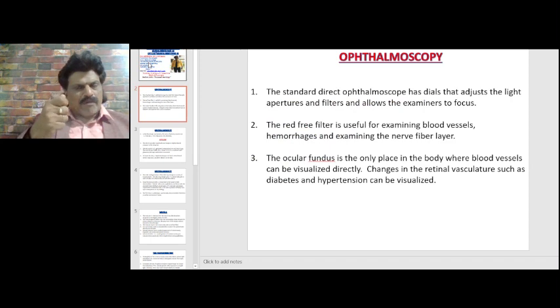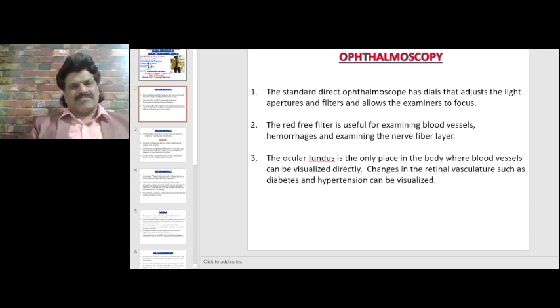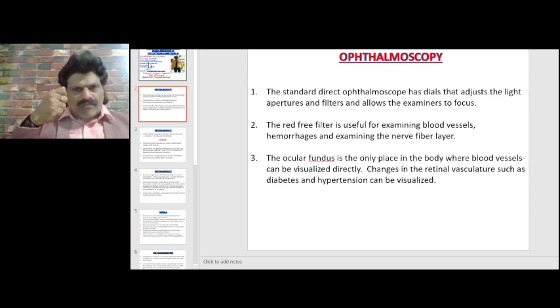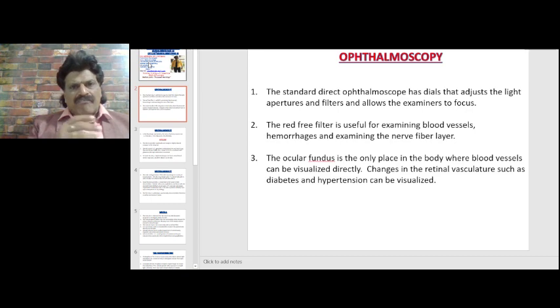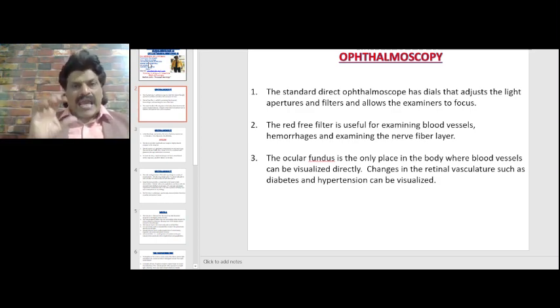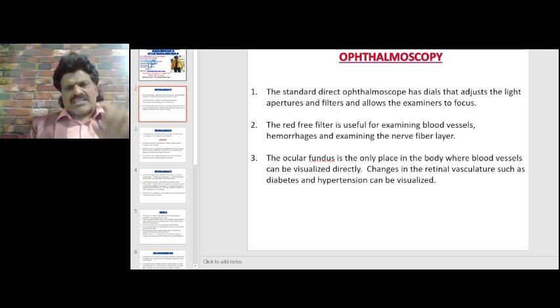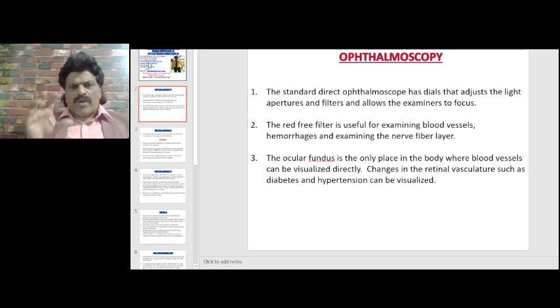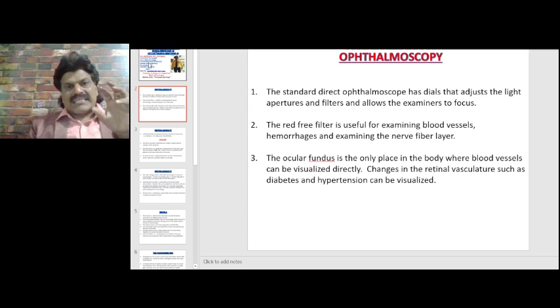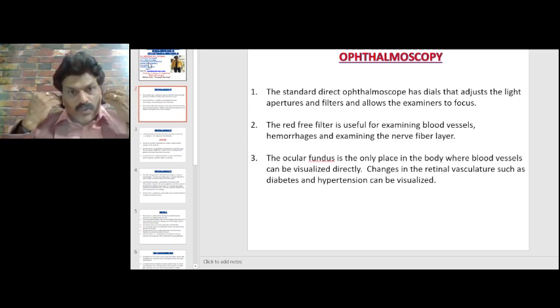The ophthalmoscope is an equipment used by neurologists and ophthalmologists to see the ocular fundus. The standard direct ophthalmoscope has dials that adjust the light apertures and filters and allows the examiners to focus. The red-free filter is used for examining the blood vessels, hemorrhages, and the nerve fiber layer. The ocular fundus is the only place in the body where blood vessels can be visualized directly, so changes in the retinal vasculature such as in diabetics and hypertension can be visualized directly.